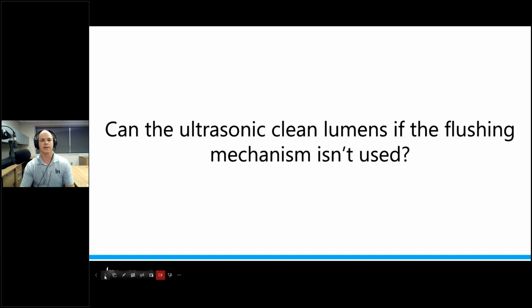So be aware of that. And then on the side panel, we open up the side panel. This is the front panel. There's a side panel. We find this pump inside here. This pump is what takes water from the inside of the tank and flushes it through that lumen cleaning circuit, and basically is responsible for that function in the ultrasonic. So it has nothing to do with the generator or the transducers. This is a whole separate piece of equipment.